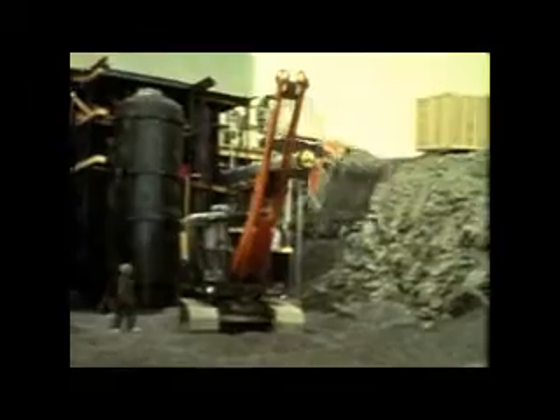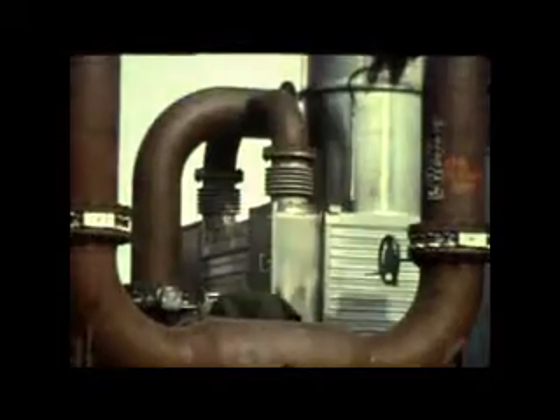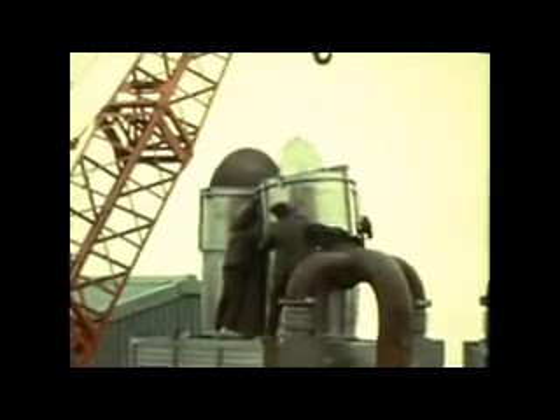As work goes on, snow — another reminder that winter is never far off. Work must not stop, and inside, away from the weather, conditions are better. The turbine generator is installed in the center of the building. The switchgear distributes the power output of the generator through the nearby substation to the McMurdo base. Outside, we are installing the condensers, which receive the exhaust steam from the turbine. They are direct air-to-steam type and need no liquid coolant. Water flows out of them into the hot well, is de-aerated and heated by the heat transfer equipment, and returned to the steam generator for another cycle. The plant contains its own complete laboratory for analysis of system water and a control area for the decontamination of equipment and personnel.